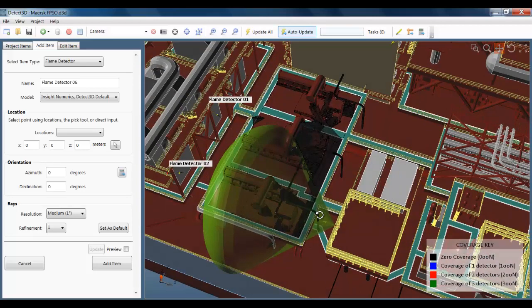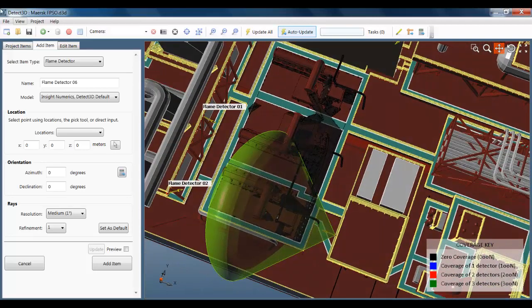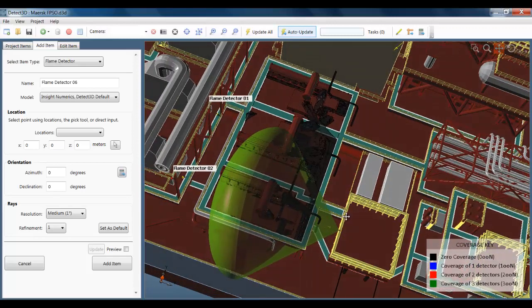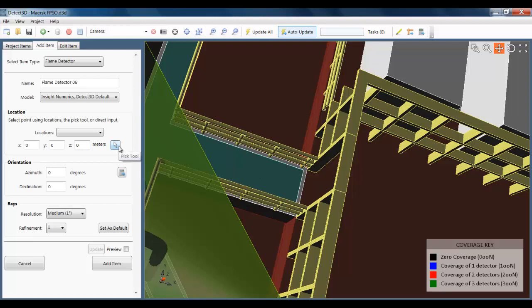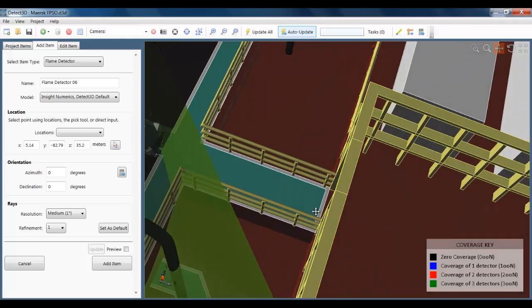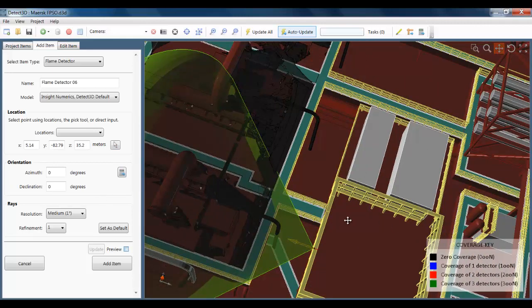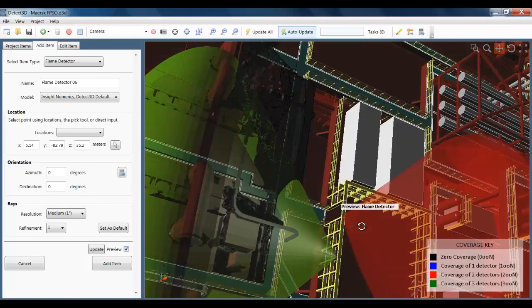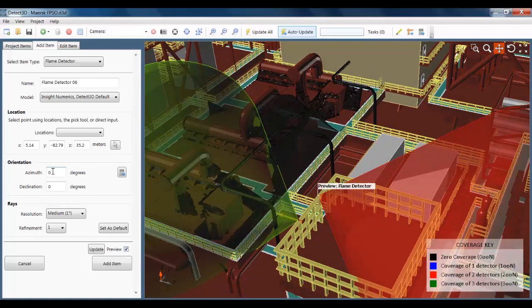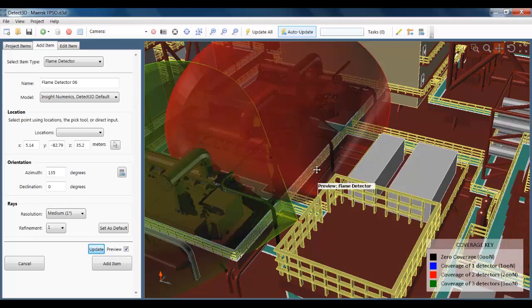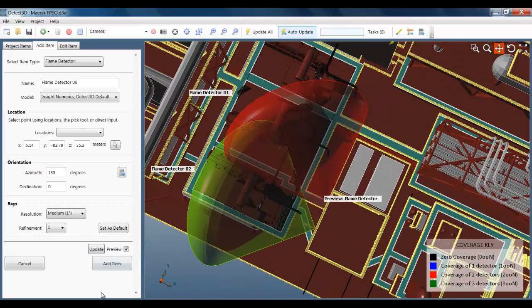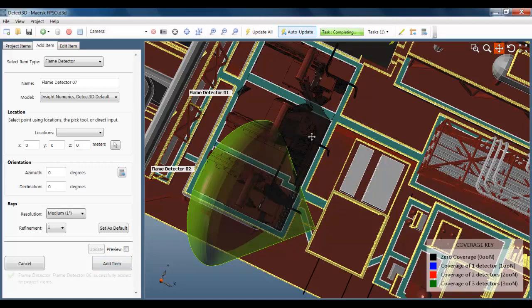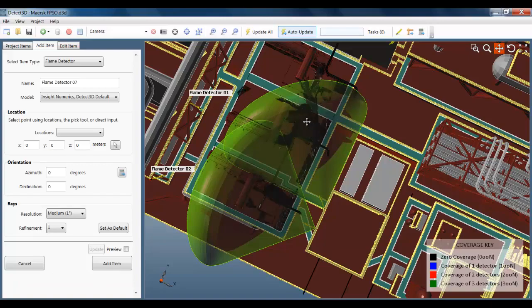Now, just take a look at this blind spot here. You can see that it's updated in real time, which is a really nice feature of the software. You can actually really see the effect that each flame detector has as you're doing the project. So as you're placing flame detectors and updating the analysis, you can actually see the results updating and feeding back to you how well the flame detector layout is performing. This is the final flame detector I'm going to add. I'm just going to swivel that round to point towards this blind spot. Again, the declination is good enough, so I'm just going to add it. And again, let's have a look at that blind spot to see if it's updated.